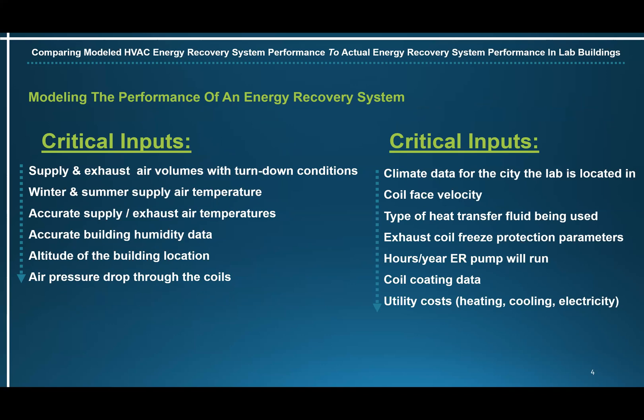Critical inputs: supply and exhaust air volumes with turndown conditions, winter and summer supply air temperature, accurate supply and exhaust air temperatures, accurate building humidity data, the altitude of the building location, the air pressure drop through the coils, the climate data for the city the lab is located in, coil face velocity, and type of heat transfer fluid being used.